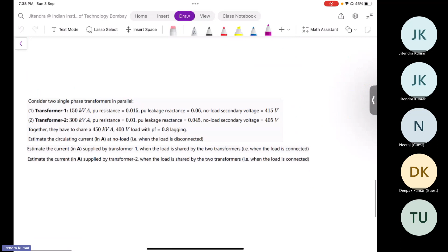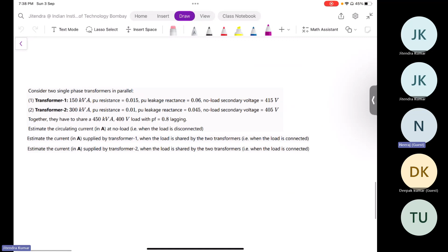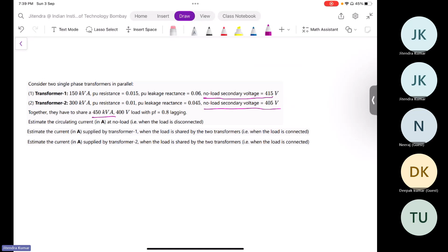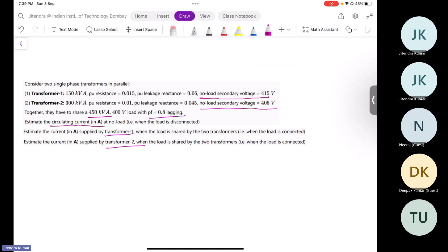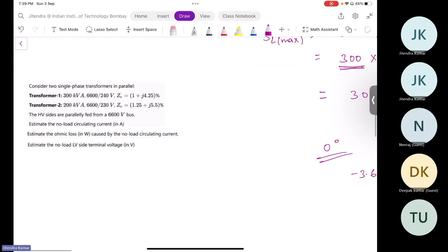In this part 3 problem, we have circulating current. I am not going to solve this problem because it will again take very high time. It is based on the circulating current equivalent circuit, because no load voltages are different. So again, they are sharing certain load with a certain power factor, which is pretty common here. First you need to calculate the circulating current, which is pretty easy. In part B, the complexity arrives in finding what percentage of load is shared by transformer 1 and transformer 2, similar to the problem solved in part B of the first problem.